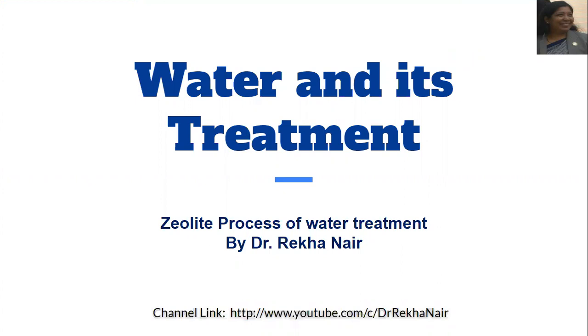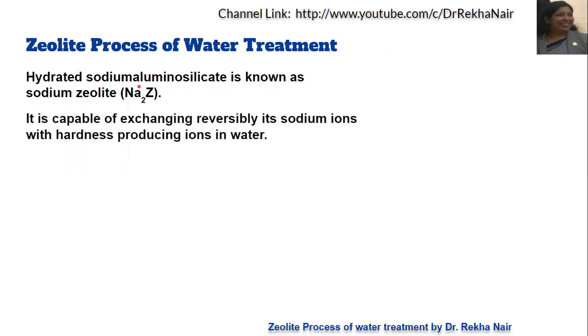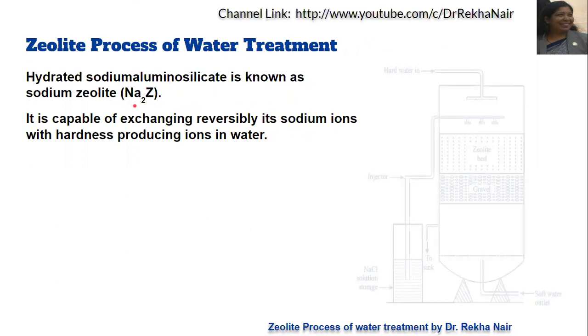We have a better residual hardness in the case of the zeolite process. In the zeolite process, we use zeolite — that is hydrated sodium aluminosilicate — which we write as sodium zeolite, Na₂Z. This is capable of reversibly exchanging its sodium ions with the hardness-producing ions in the water, meaning the sodium ions will be replaced by calcium and magnesium ions present in the water.